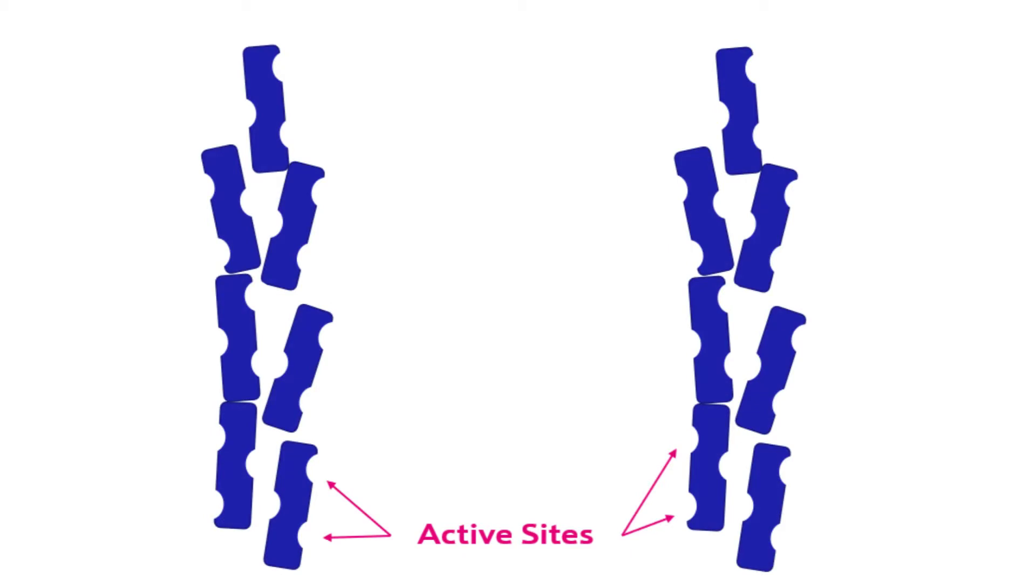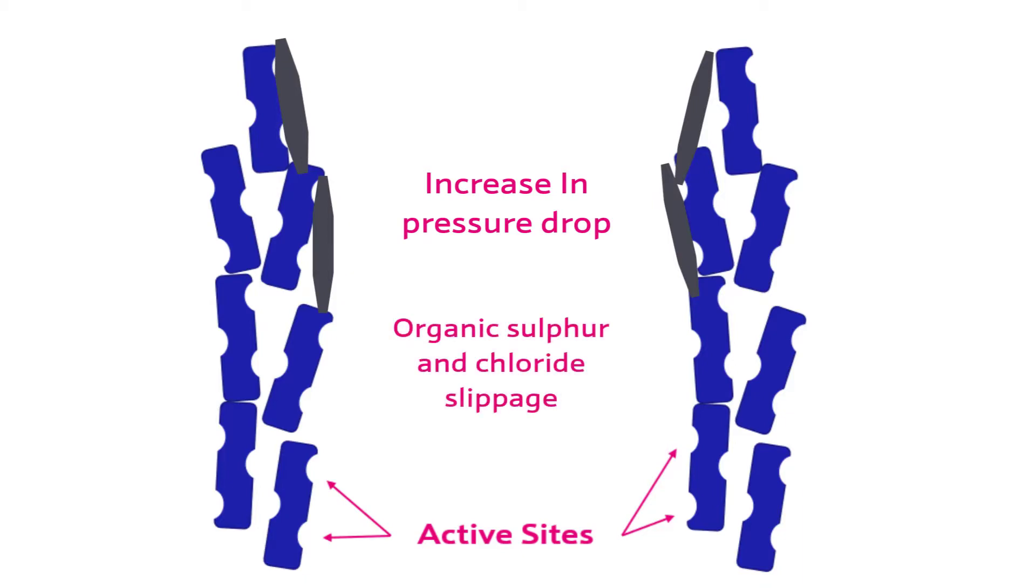There are several methods with which the HDS catalyst can become deactivated. One of the most common is carbon formation, which can occur in both the preheat coils and the top of the bed. When this occurs, carbon blocks the active sites of the catalyst, inhibiting the HDS reaction. A sign that this form of deactivation is occurring is an increase in pressure drop across the bed and organic sulfur or chloride slippage.